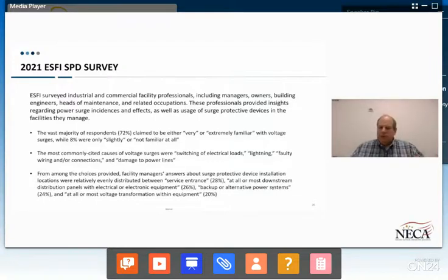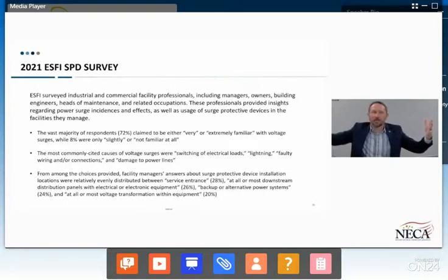Maybe I'll let Jack speak to that. Thank you, Keith, I completely agree, and we see that in the field all the time. It makes sense because when a lightning event happens or a car hits a telephone pole, you immediately see a failure. Whereas internally generated transients are harder to track — we call it death by a thousand cuts. It's not like a motor kicking on once will knock out your fire alarm panel; it takes time. It's slowly chipping away at the dielectric strength at the weakest component on the board, or chipping away at the insulation on your windings, until eventually you have a failure.